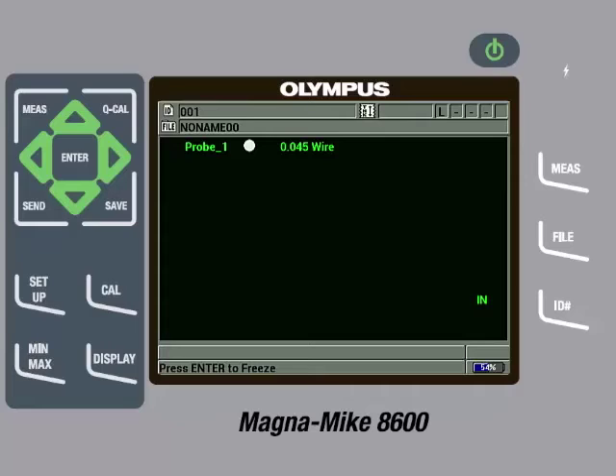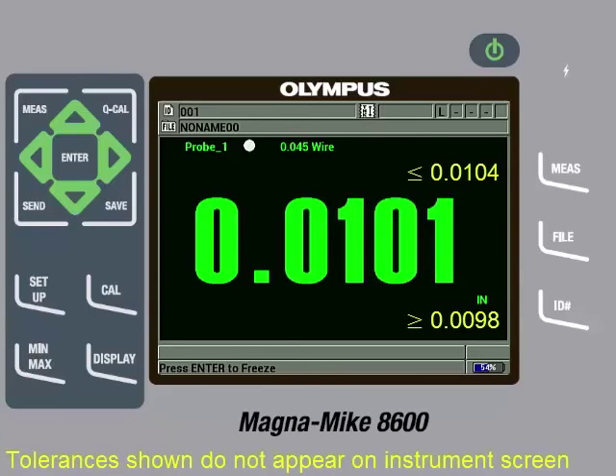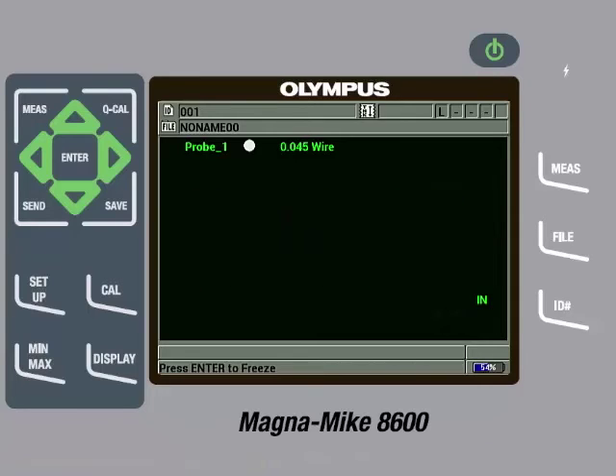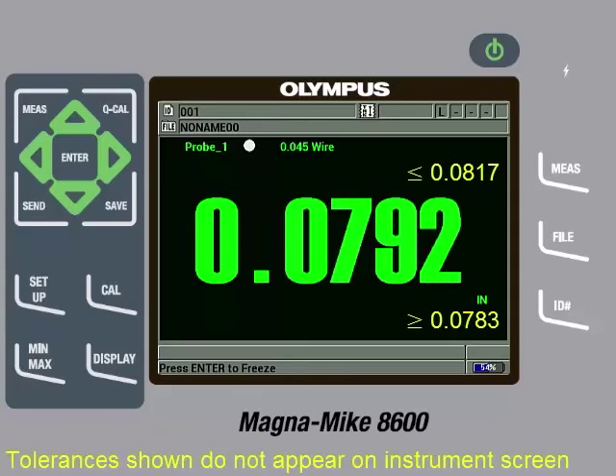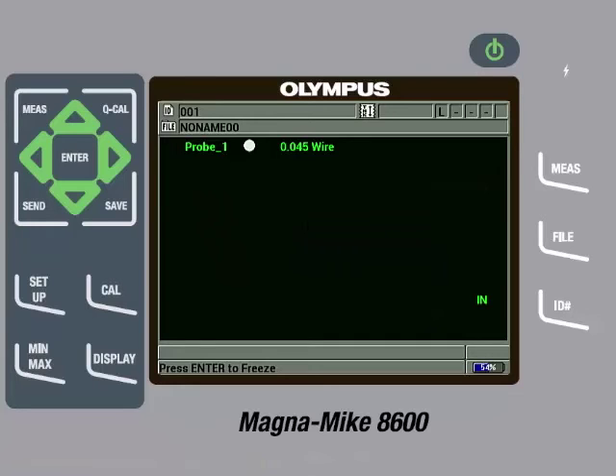It is good practice to check a few of the reference standards after the calibration has been completed to make sure they are measuring within specification. If they are not, you can try removing the target from the probe tip and then pressing the Q-Cal key. We will check the 10 thousandths of an inch shim to make sure it is measuring within specifications, which it is. Then we will check the 80 thousandths of an inch shim to make sure it is measuring within specifications, which it is.